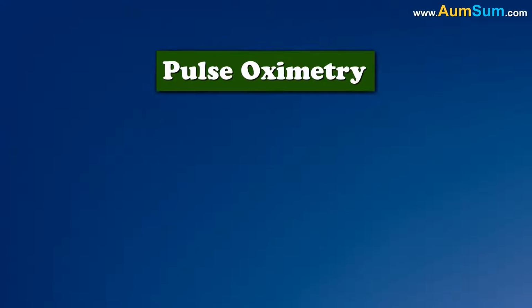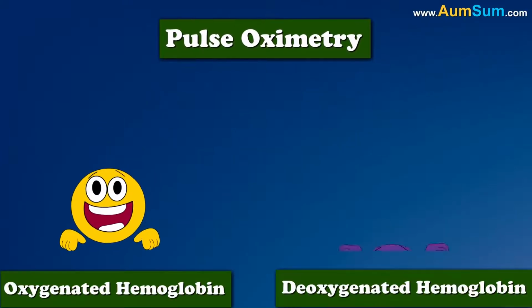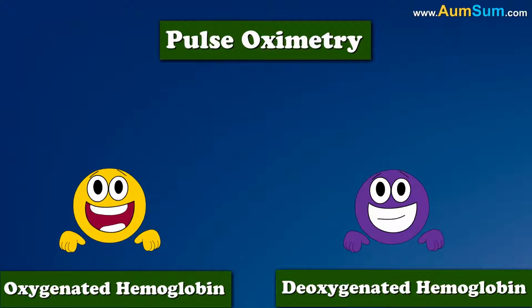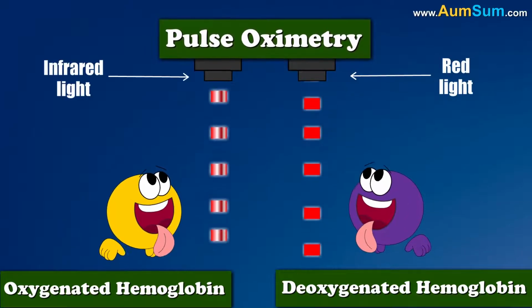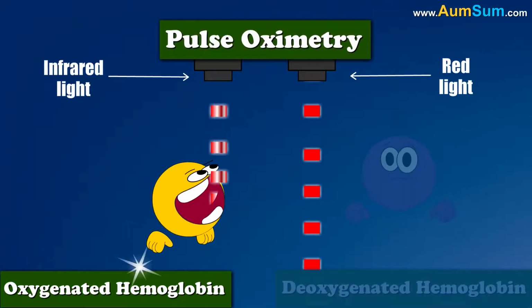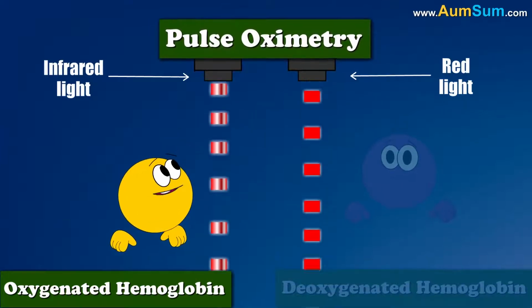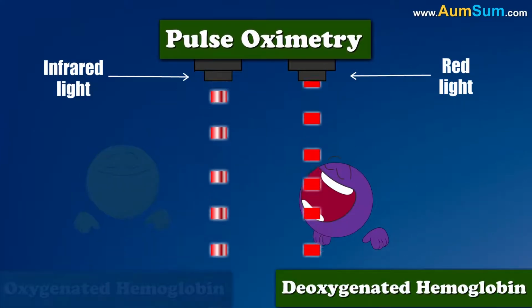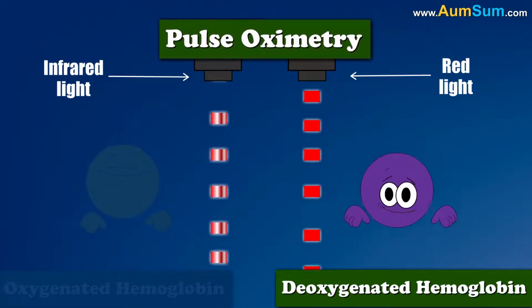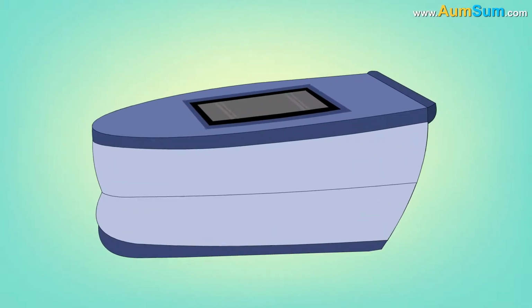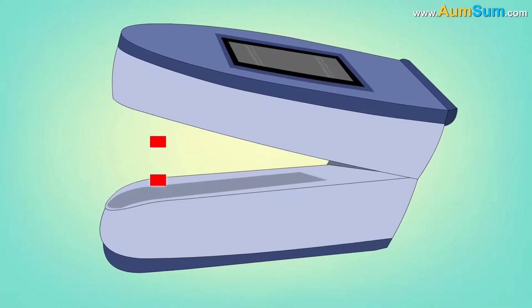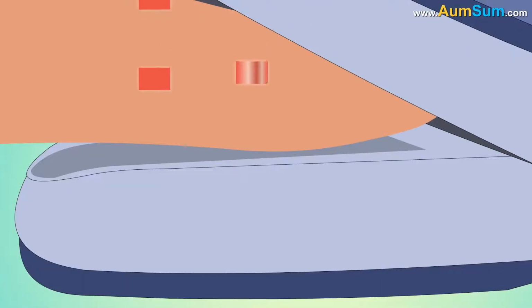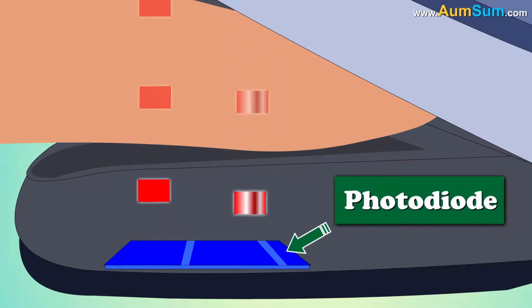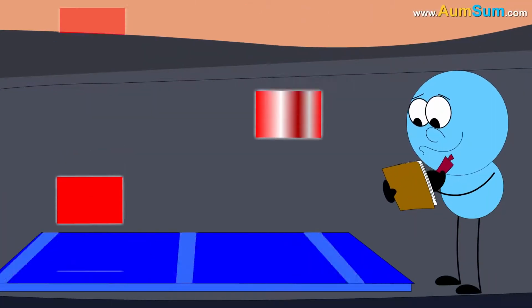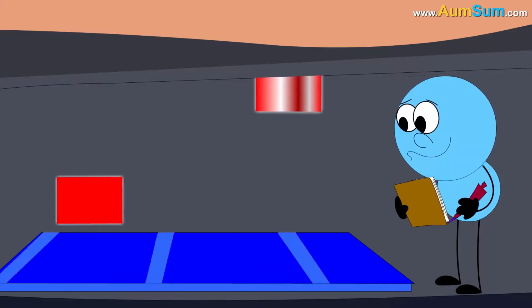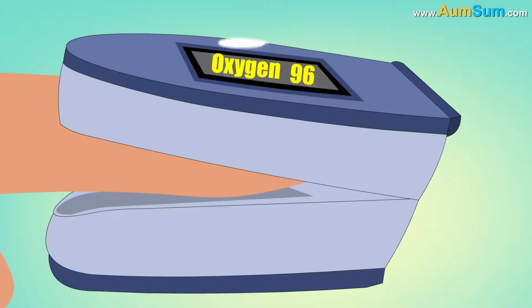Pulse oximetry is based on the principle that oxygenated hemoglobin and deoxygenated hemoglobin differentially absorb red and infrared light. Oxygenated hemoglobin absorbs greater amounts of infrared light and lower amounts of red light as compared to deoxygenated hemoglobin. Now, a pulse oximeter has LEDs which emit red as well as infrared light. These lights pass through our finger and are detected by a photodiode on the opposite end. Finally, by measuring changes in the light absorption, a pulse oximeter is able to give us the oxygen level in our blood.